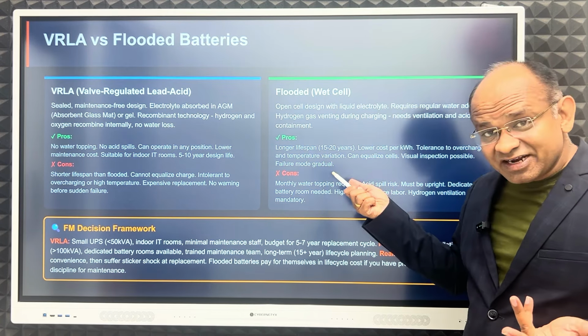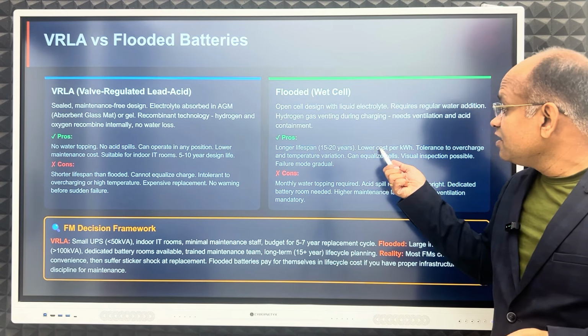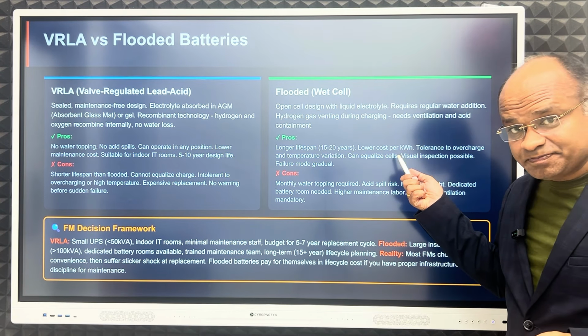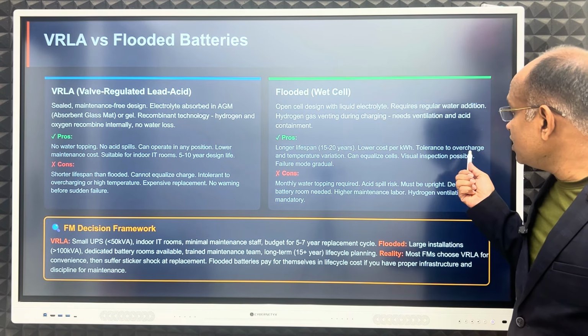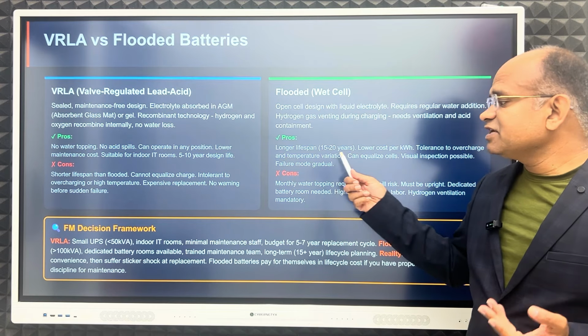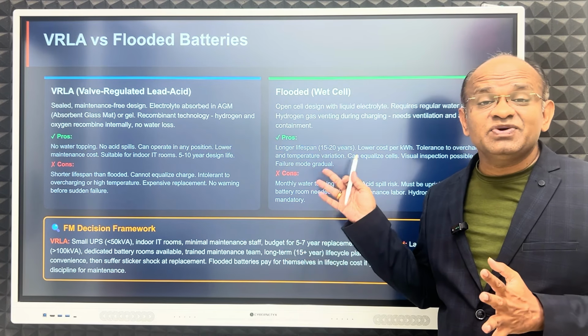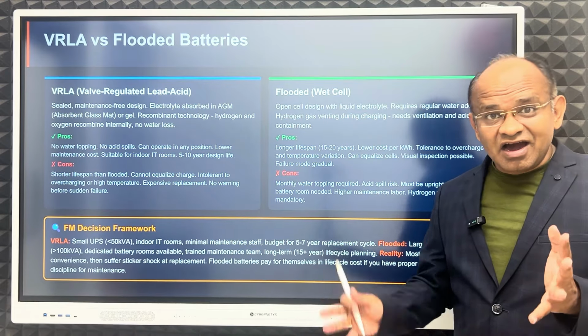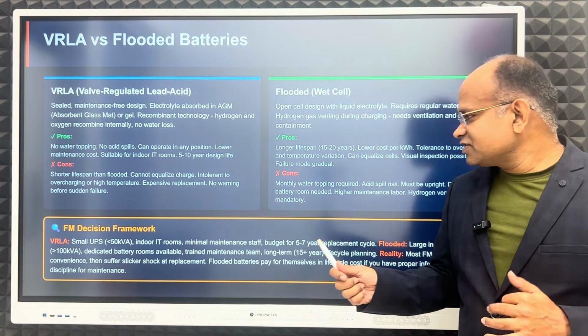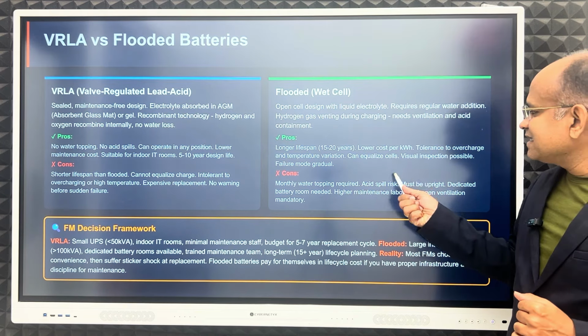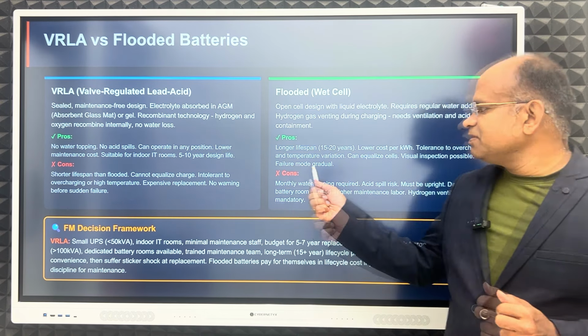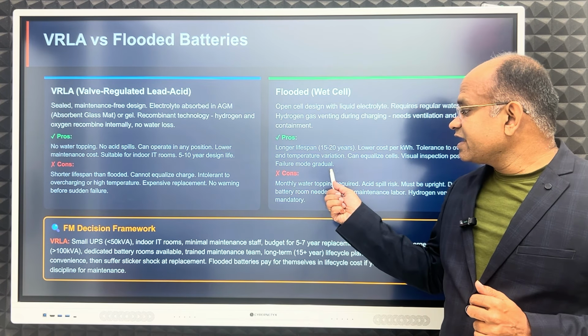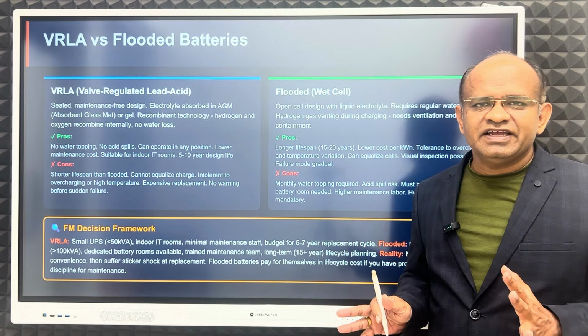Pros of flooded batteries: longer lifespan, 15 to 20 years, lower cost per kWh, tolerance to overcharge and temperature variations - that is why these were used in cars or old trucks. They can also equalize cells, visual inspection is possible, and failure mode is gradual, slowly failing, not directly.